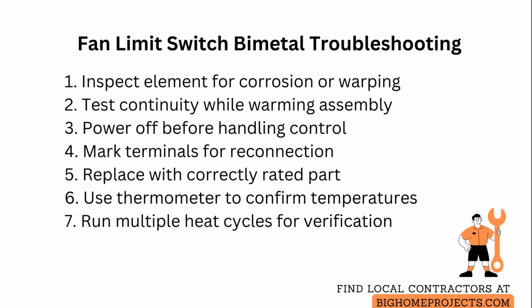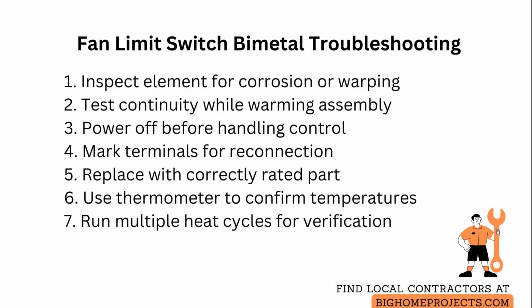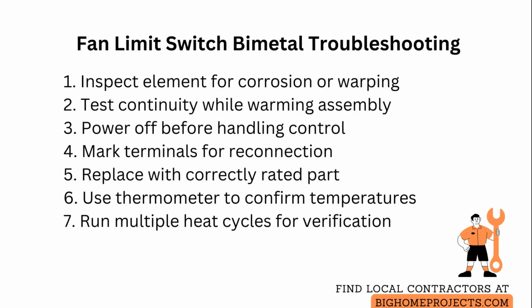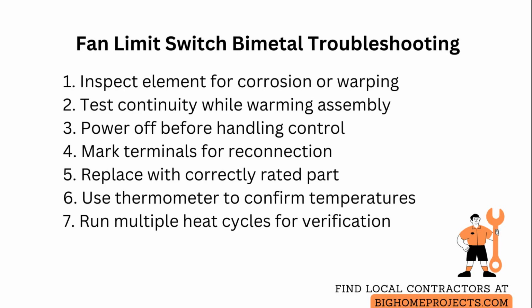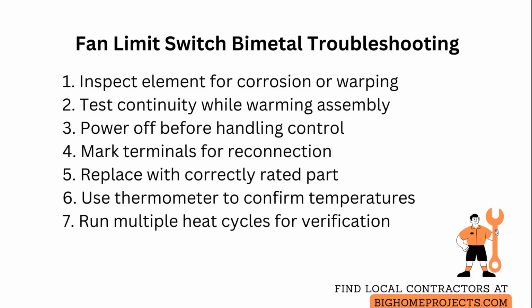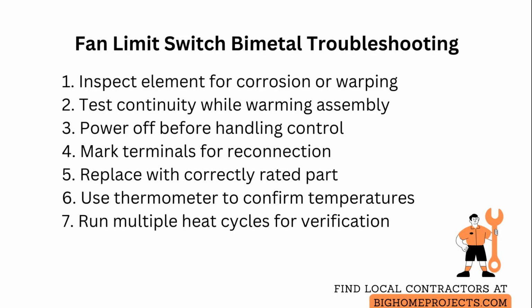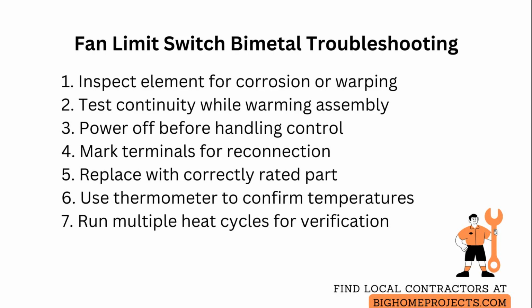Inspect the element visually for corrosion, thinning or warped curvature, and test electrically by measuring continuity as the assembly warms. If continuity fails to change at the expected temperature, the element has degraded. Remove power to the furnace before handling the control, mark terminal positions for reconnection, and substitute a correctly rated replacement part matched to the original switch specifications to restore designed operating points.